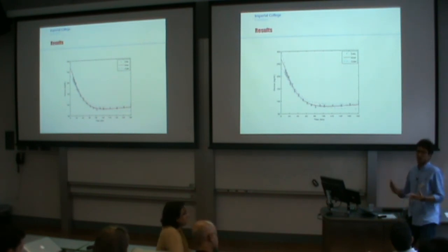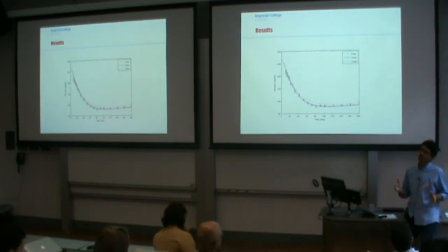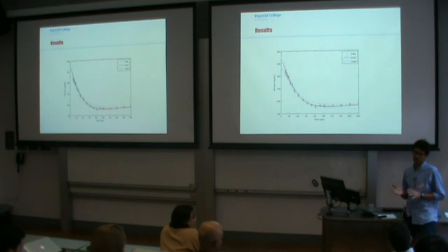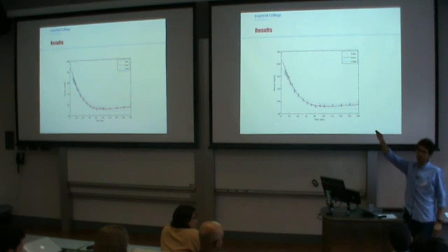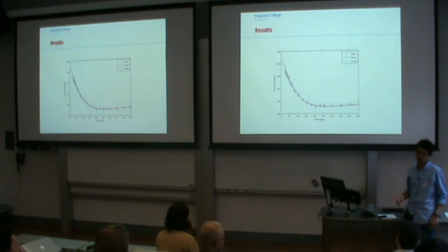So you have kind of real dynamics, and we did the tests, and for these delays we have an average delay for the detection of a pump occlusion of maybe 2 hours. It's quite long because the dynamics are very slow in this problem. But even with a 2 hour delay in the detection, the glucose levels that we were reaching were not dangerous. So it's acceptable. It's not like I go to 500 milligrams per deciliter, that is critical. It's like 200, that is okay.